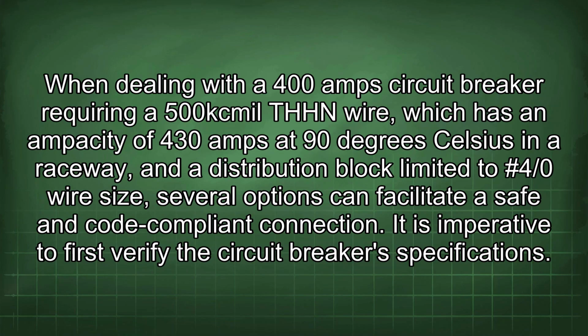When dealing with a 400 amp circuit breaker requiring a 500 kcmil THHN wire, which has an ampacity of 430 amps at 90 degrees Celsius in a raceway, and a distribution block limited to #4/0 wire size, several options can facilitate a safe and code-compliant connection.